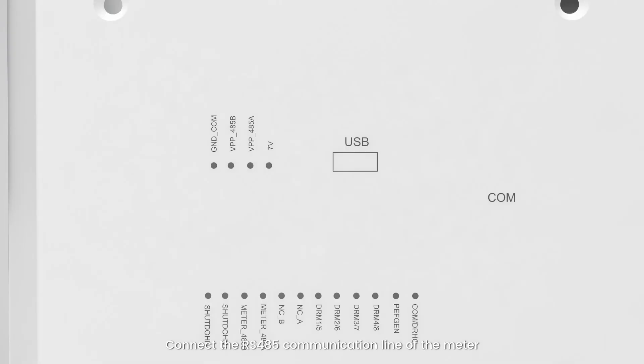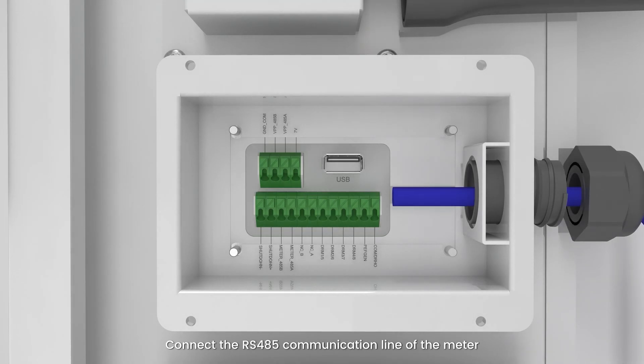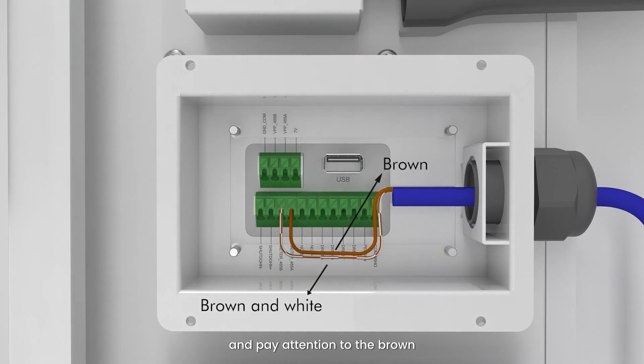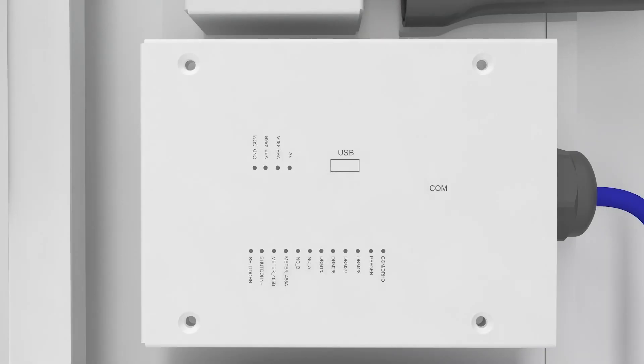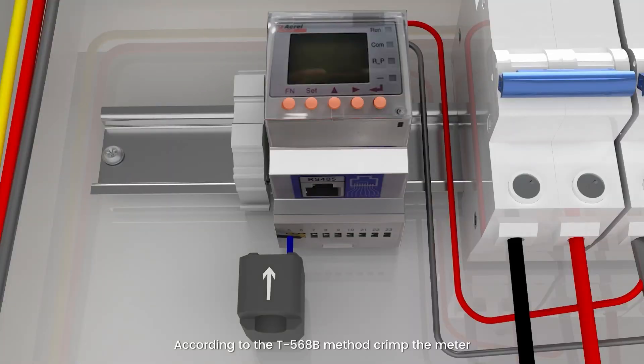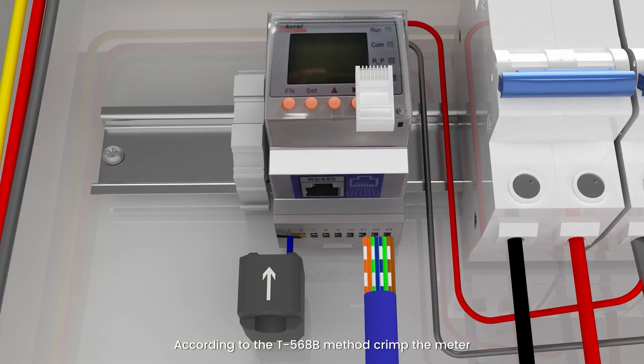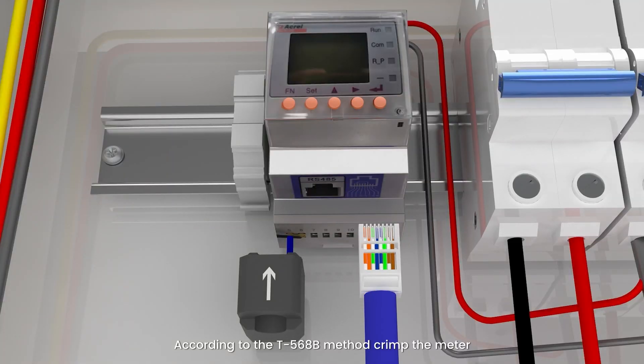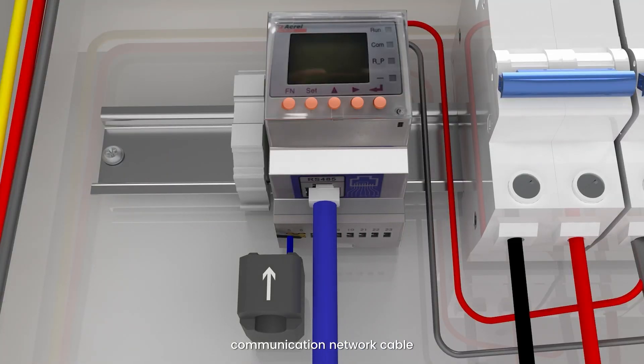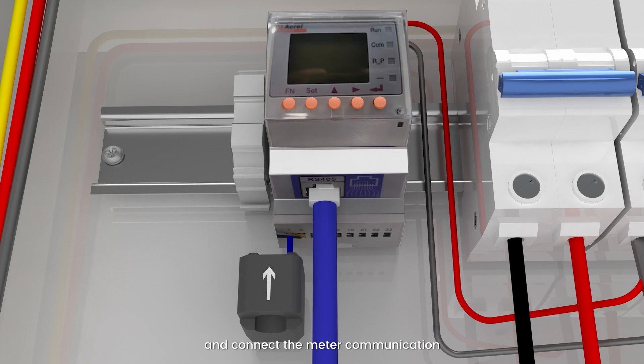Connect the RS-485 communication line of the meter and pay attention to the brown and white and brown connections. According to the T568B method, crimp the meter communication network cable and connect the meter communication.